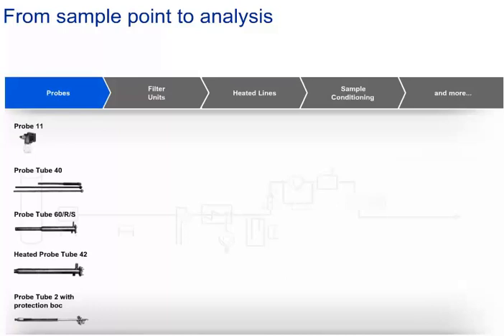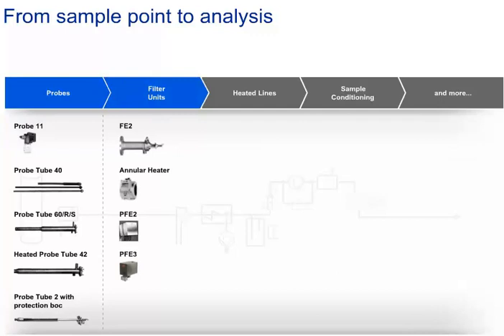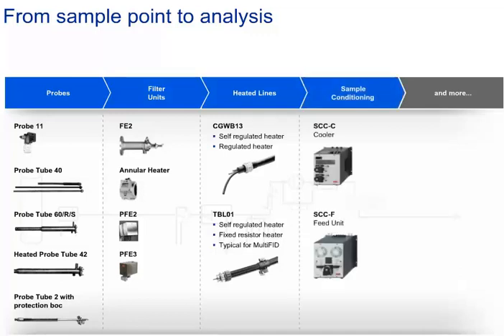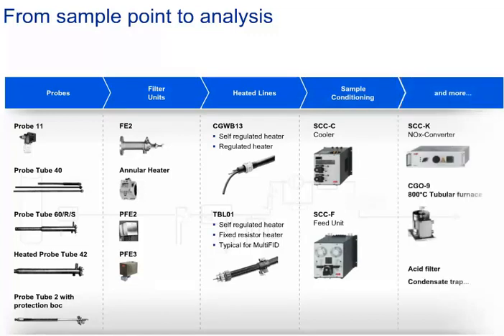The product range includes: various probes made from suitable materials in different lengths; special filter units that remove dust particles directly at the sample point; heated lines in various lengths to transport the sample gas safely to the analysis shelters without condensation; process-proven coolers and pumps; and gas converters, furnaces, and acid filters that help prepare sample gases from difficult mixtures so that they can be measured with common sensor technologies.